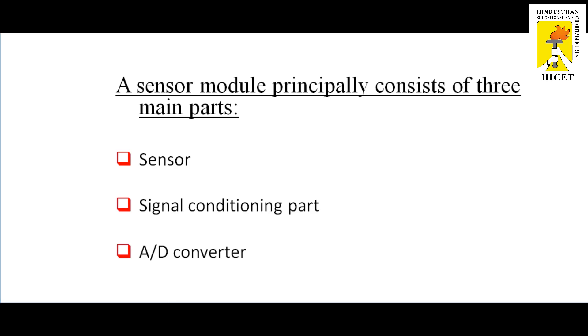The sensor detects physical signals from the environment. If the parameter being measured is not electrical, the sensor must include a transducer to convert the information to an electrical signal. The signal conditioning module performs signal conditioning prior to analog to digital conversion. This module usually does amplification, transducer excitation, linearization, isolation, or filtering of detector signals. The analog to digital converter changes the detected and conditioned voltage into a digital value. The converter is defined by its resolution and sampling frequency. The converter data must be precisely timestamped to allow later sophisticated analysis.